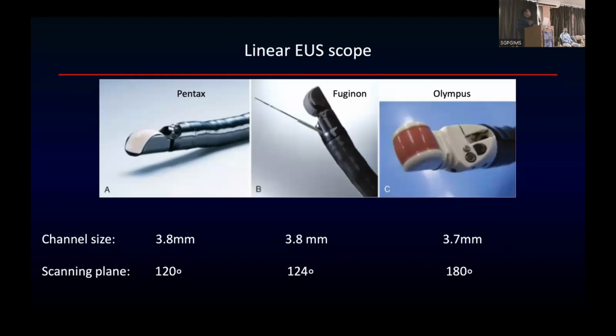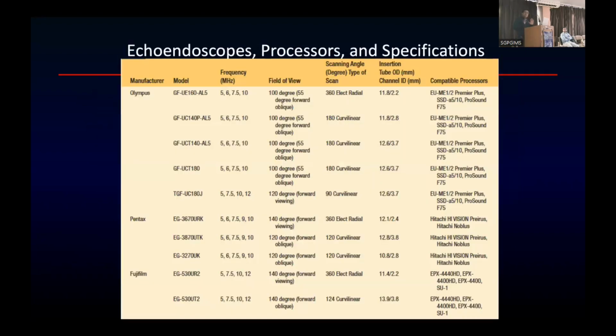So what does this scanning plane mean? Scanning plane is primarily the whole angle along which you are imaging that particular lesion. Does that make a difference? Yes, it does. When you are looking at a particular area, you have more area of visualization on the EUS image. That's the difference with the scanning plane, which is maximum with Olympus, and Pentax and Fujinon are almost similar. So this chart tells you the frequency with Olympus ranges from 5 to 10. With Pentax, it again is from 5 to 10, and with Fujinon, it goes up to 12. So you have a maximum frequency of 12 available with Fujinon. Does that make a difference? Yes, it does, because you are better able to get resolution when you are imaging a particular lesion.